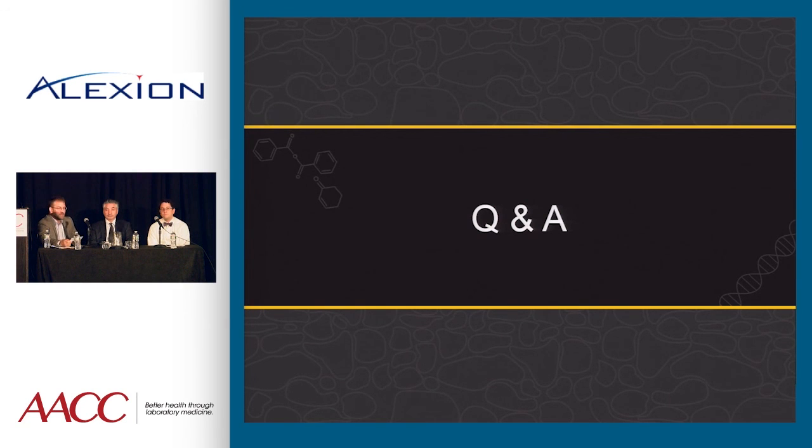So if you look at the CLSI guidelines, ideally you try to find 20 healthy individuals, and if you run those, and as long as 18 out of the 20 fall within the interval that you wish to adopt, then you can adopt that interval. But finding 20 healthy kids means male, female, all of those different categories for whatever analyte you're looking for. And in our case, sometimes we're not looking at just 20 kids, we're looking at 40 at a minimum, so we get male and female, but then all those different age categories that it may fall into. So I may be looking at several hundred or 1,000, and that's where it becomes difficult to do that verification.